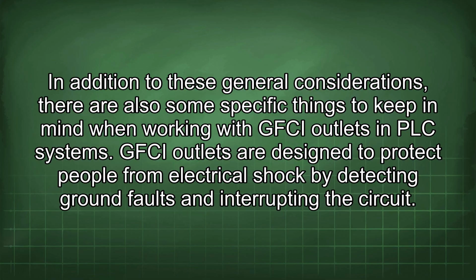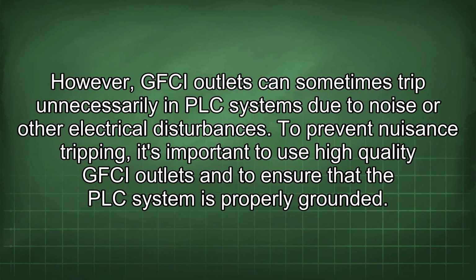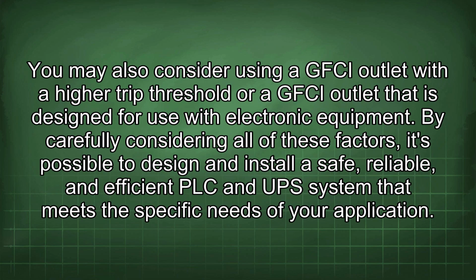GFCI outlets are designed to protect people from electrical shock by detecting ground faults and interrupting the circuit. However, GFCI outlets can sometimes trip unnecessarily in PLC systems due to noise or other electrical disturbances. To prevent nuisance tripping, it's important to use high-quality GFCI outlets and to ensure that the PLC system is properly grounded. You may also consider using a GFCI outlet with a higher trip threshold or a GFCI outlet that is designed for use with electronic equipment.